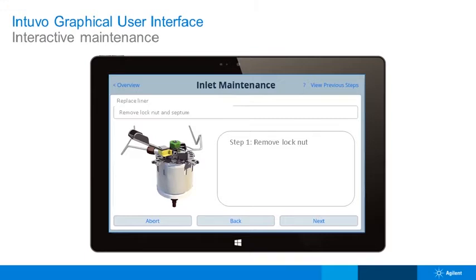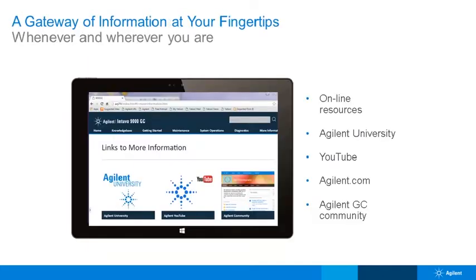It will turn off the gas supply when the areas that need to be cool are cool. It will then give you step-by-step instructions on how to do that maintenance. And then once the maintenance is done, i.e. you have now changed the liner, it will do the leak check like I've just said previously. And then effectively it has automatically started the timer, which means that you know how many injections are done down that liner. So you know when you actually need to change it again. So you can set that maintenance timer, and it obviously depends on what analysis you're doing, but that maintenance timer will then tell you when the next liner should actually be changed.